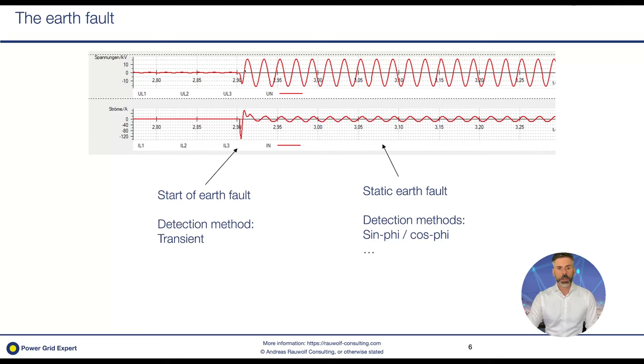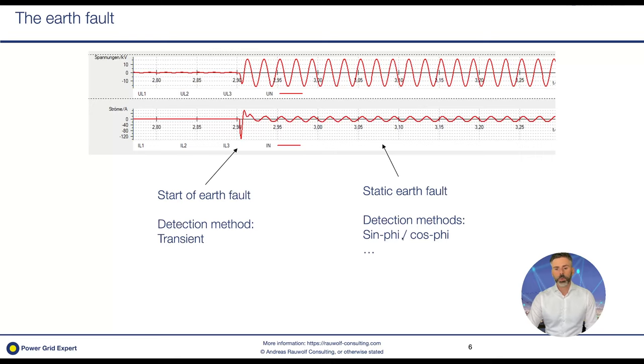The detection devices have to be quite quick to detect the fault. If the earth fault persists in the network, we have the so-called static earth fault: a 50 Hz zero sequence voltage and a 50 Hz zero sequence current. These signals are used to find the fault. Transient detection only looks at the transient at the beginning, while static methods look at the 50 Hz signal. Today we focus on the sin-phi and cos-phi methods, the most commonly used static methods, though more methods are available.